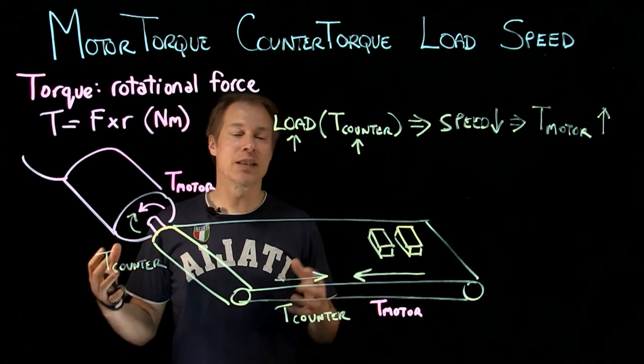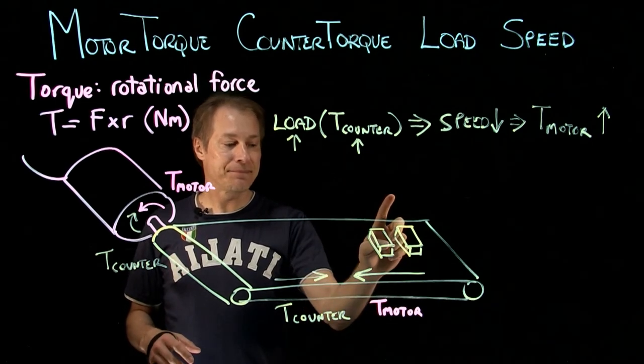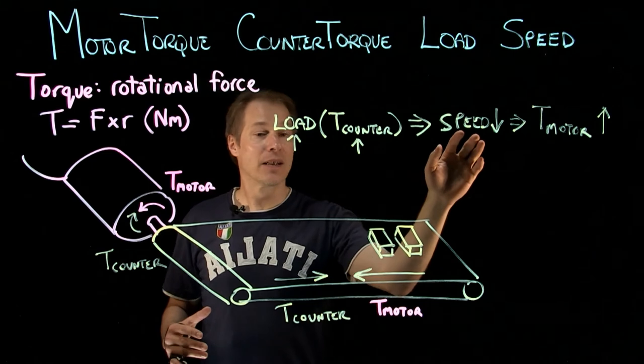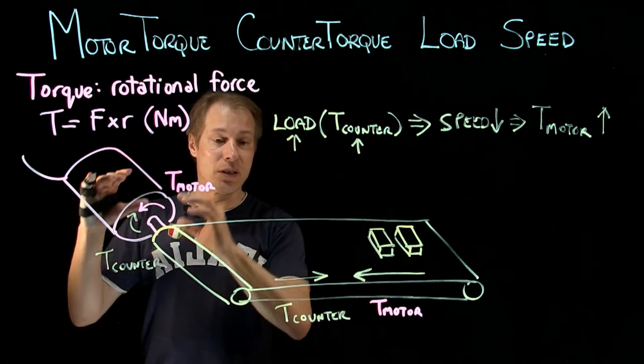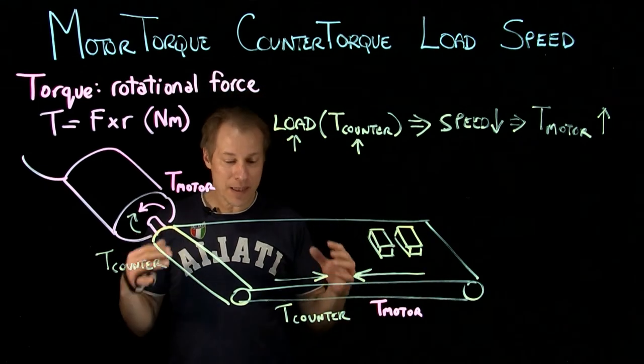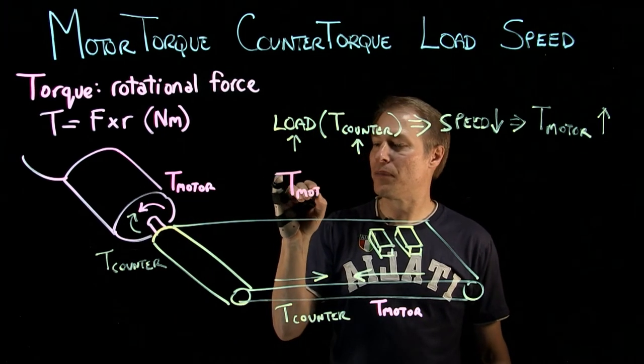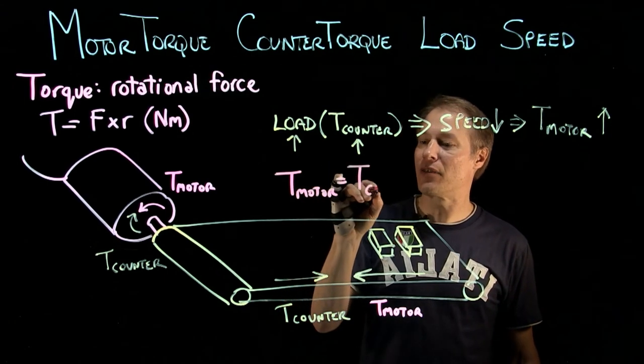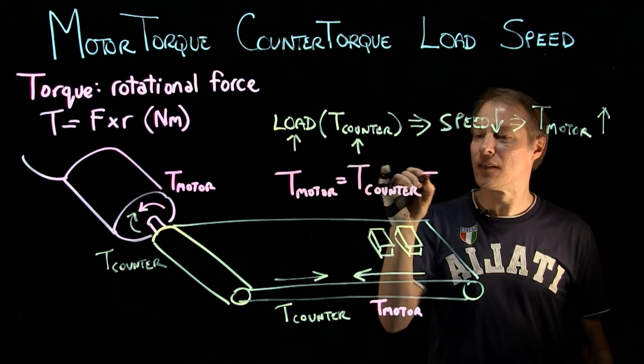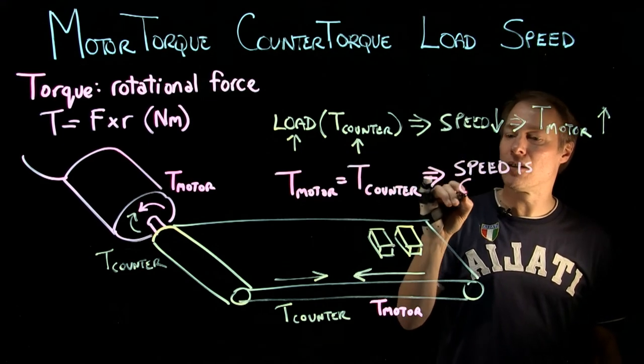Let's look at this daisy chain again. As load goes up, the counter torque goes up — that's the torque acting against the motor torque — which brings down the speed of the motor. When the speed of the motor goes down, the torque of the motor goes up. What ends up happening is when the motor torque equals the counter torque, the speed stabilizes and becomes constant.